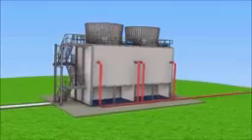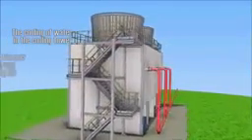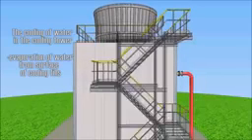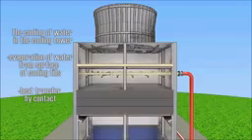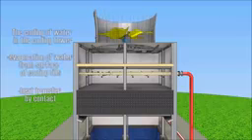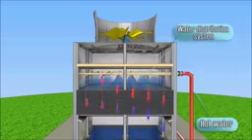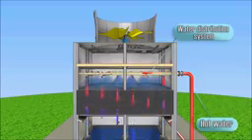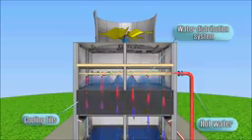So, how does the cooling tower work? Water in cooling towers is cooled by evaporation of water in the stream of atmospheric air, with heat transfer by contact with air. Hot water from various sources such as machines or heating processes flows through pipes to the distribution system of the cooling tower, which produces even water distribution over all the area of the fills by the spray nozzles.